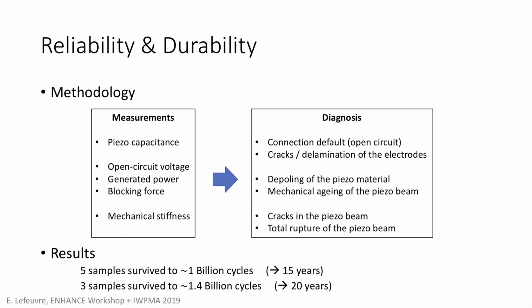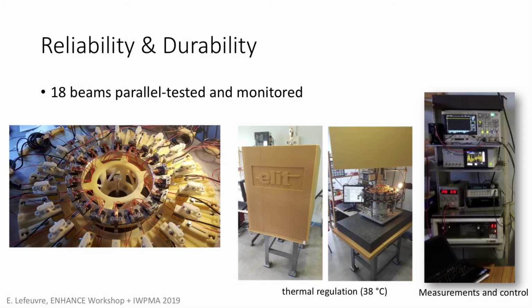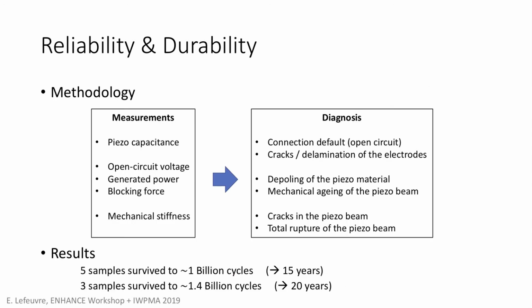And most of the time we had problems with connections. I mean these wires that disconnected due to vibrations. When you have vibration, it makes mechanical fatigue to the wire. So we had a lot of problems with that. You can solve it: once you see it, you can stop the system and fix it. But some problems we could not solve, of course.